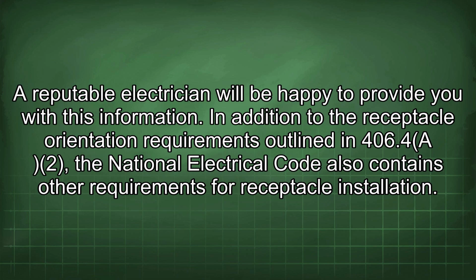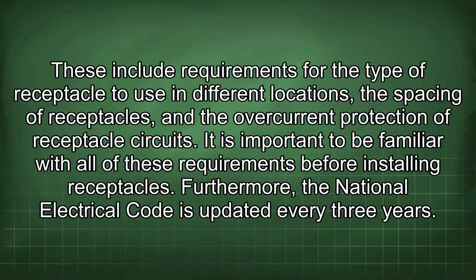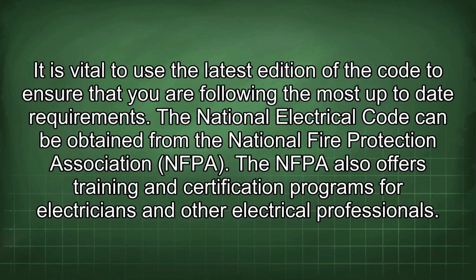In addition to the receptacle orientation requirements outlined in 406.4(A)(2), the National Electrical Code also contains other requirements for receptacle installation. These include requirements for the type of receptacle to use in different locations, the spacing of receptacles, and the overcurrent protection of receptacle circuits. It is important to be familiar with all of these requirements before installing receptacles. Furthermore, the National Electrical Code is updated every 3 years. It is vital to use the latest edition of the code to ensure that you are following the most up-to-date requirements. The National Electrical Code can be obtained from the National Fire Protection Association (NFPA). The NFPA also offers training and certification programs for electricians and other electrical professionals.